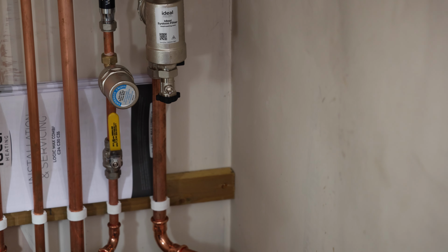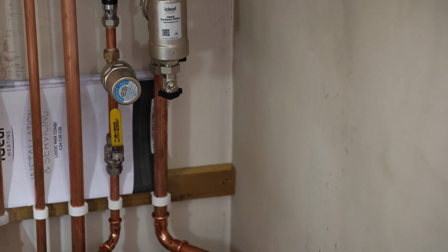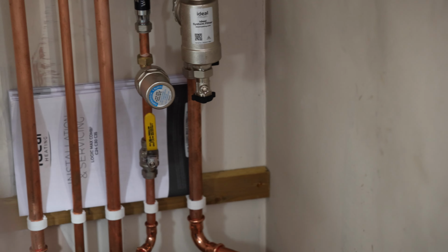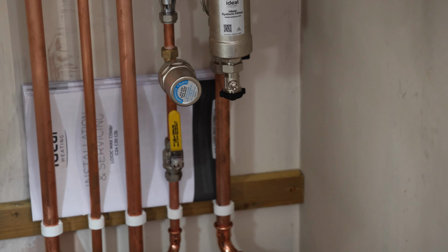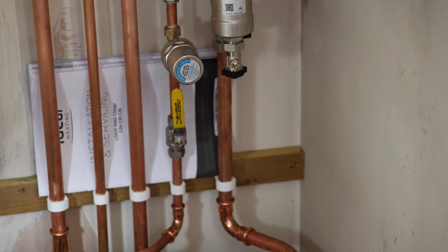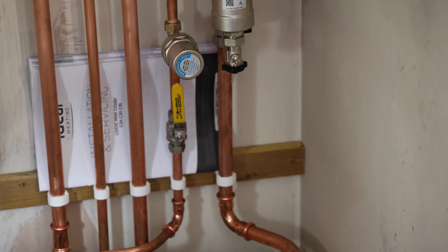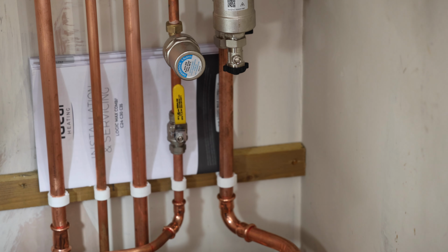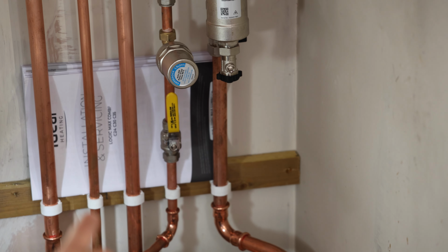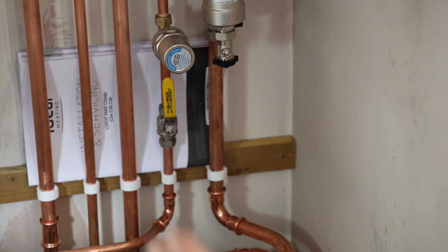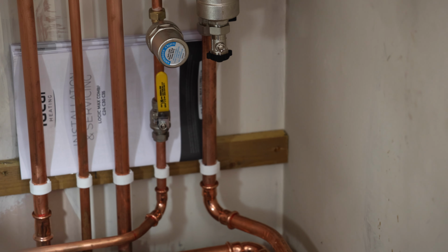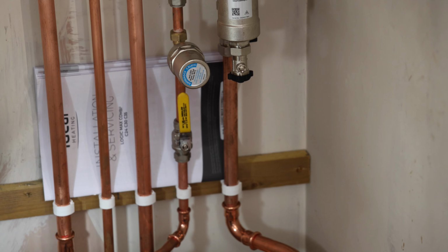And what that does, at night time when there's not a lot of water usage in the neighbourhood, is take any excess pressure from the main. That protects the boiler from suffering a split on the plastic heat exchanger or anything like that. And then at the bottom you've got a lever valve with a yellow handle. If you turn that to your right, that will isolate just your hot water.